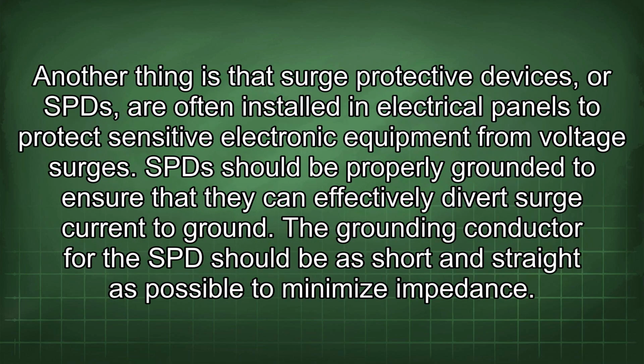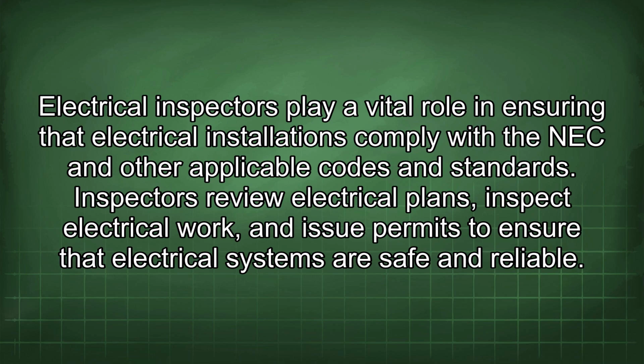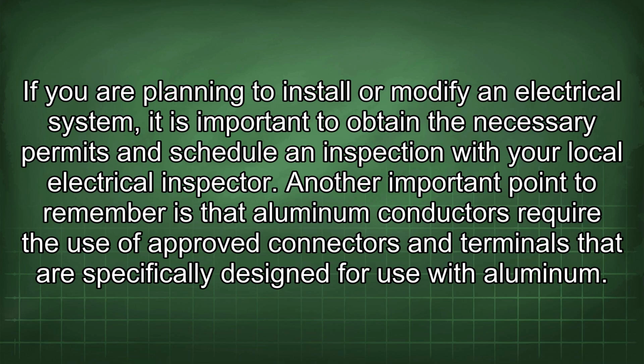Another thing is that surge protective devices, or SPDs, are often installed in electrical panels to protect sensitive electronic equipment from voltage surges. SPDs should be properly grounded to ensure that they can effectively divert surge current to ground. The grounding conductor for the SPD should be as short and straight as possible to minimize impedance. Electrical inspectors play a vital role in ensuring that electrical installations comply with the NEC and other applicable codes and standards. Inspectors review electrical plans, inspect electrical work, and issue permits to ensure that electrical systems are safe and reliable. If you are planning to install or modify an electrical system, it is important to obtain the necessary permits and schedule an inspection with your local electrical inspector.